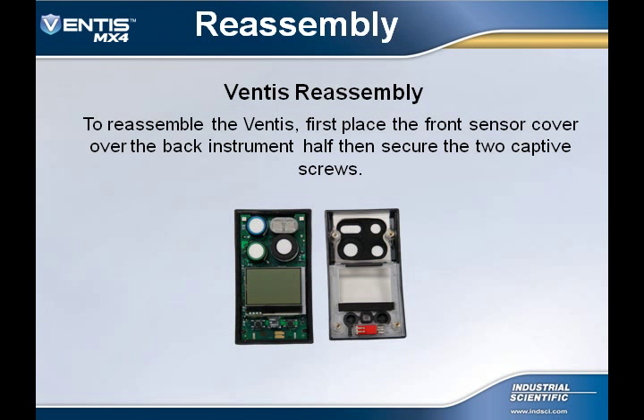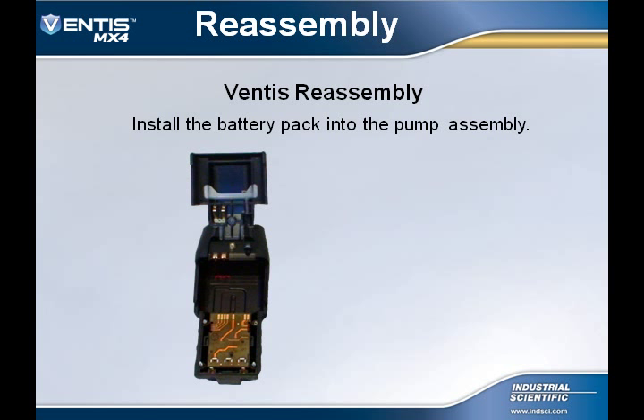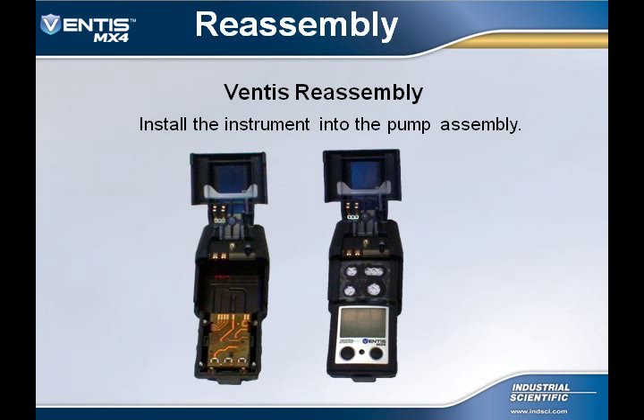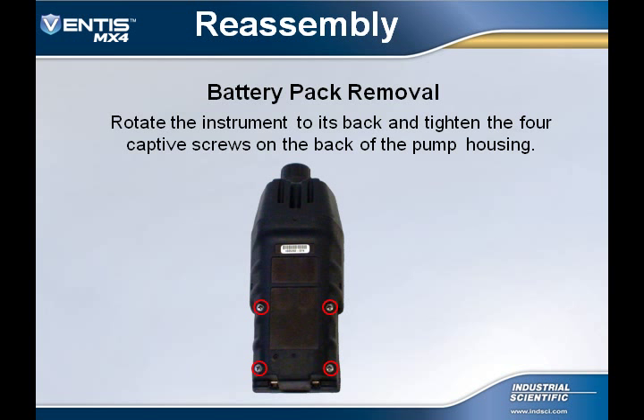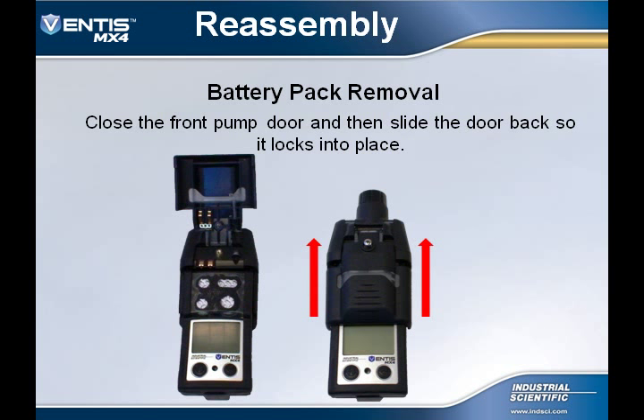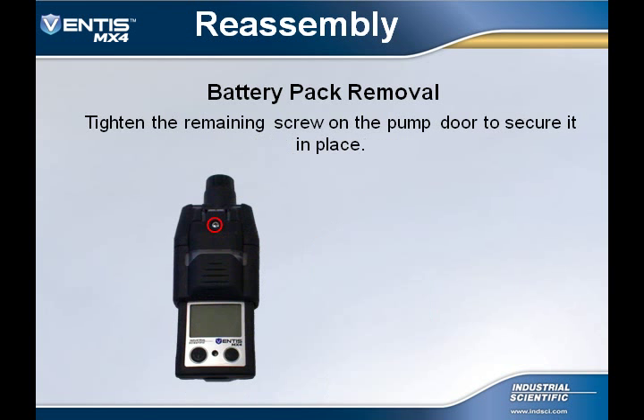To reassemble the Ventis MX4, first place the front sensor half over the back half of the instrument and secure with the 2 captive screws. Install the battery pack into the pump assembly. Install the instrument into the pump assembly. Turn the unit on its back and tighten the 4 captive screws. Rotate the instrument to its front, close the front pump door, and slide the door forward until it locks into place. Tighten the remaining captive screw on the pump door to secure.